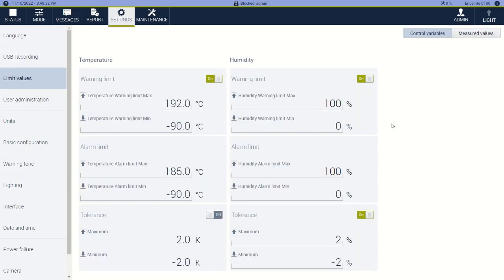Here on our limit values, this is where you can set warnings and alarms. So if you have a product that might be damaged at a certain temperature, you could set a warning to notify that you're getting close to this temperature, and an alarm to say turn the chamber off if it reaches this temperature — to protect a valuable prototype or something.